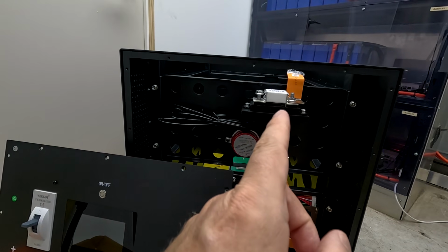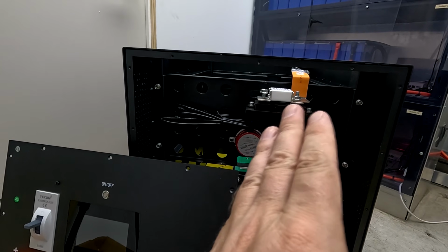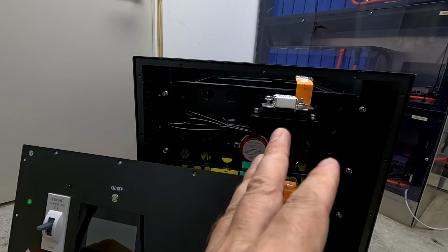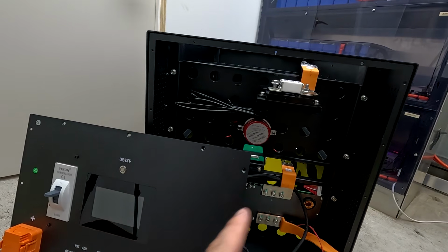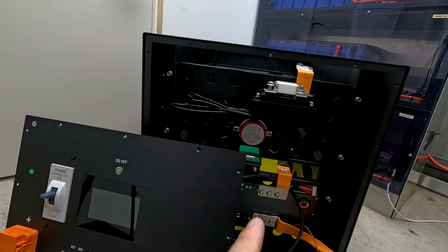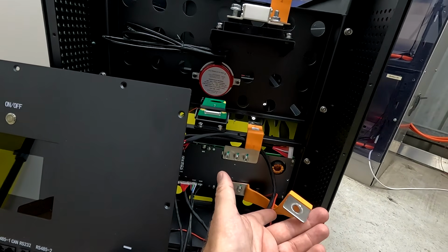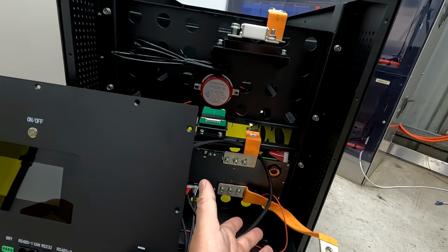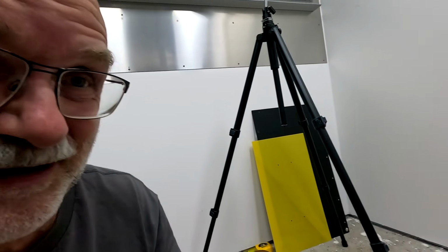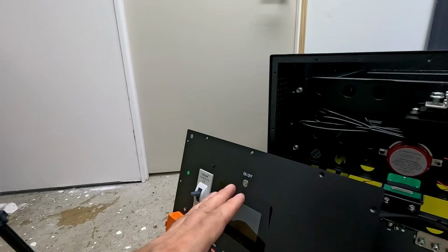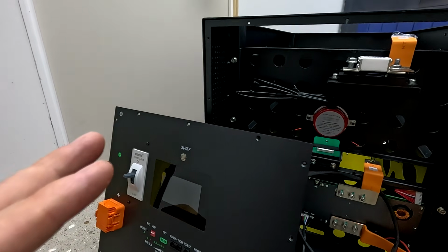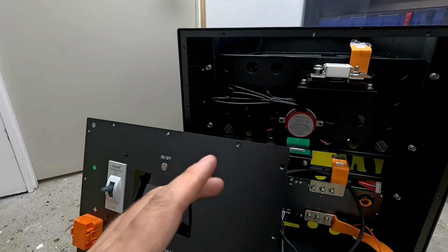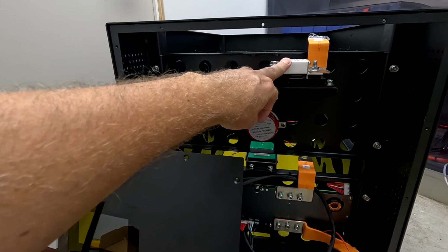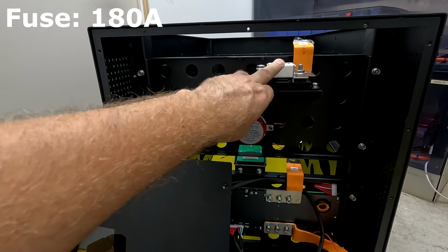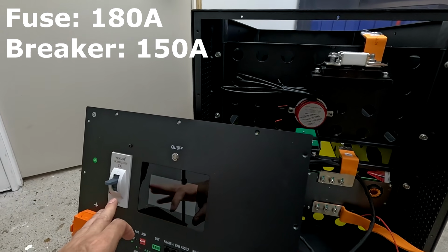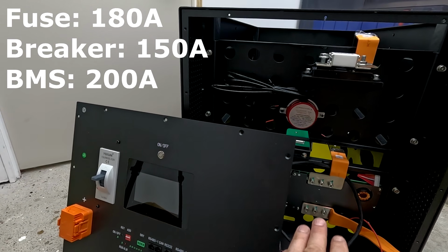The fuse is either fast or slow triggering, and they are usually fairly strict at 300 amps, so if you go a little bit over, they usually trigger. But having everything at 300 amps and then using 80 amp bus bars, I don't know, I was never a fan of these high amp circuit breakers or fuses. If I would build or design such a box, I would give it a 160, 170, 180 amp fuse, a 150 amp circuit breaker, and a 200 amp BMS.